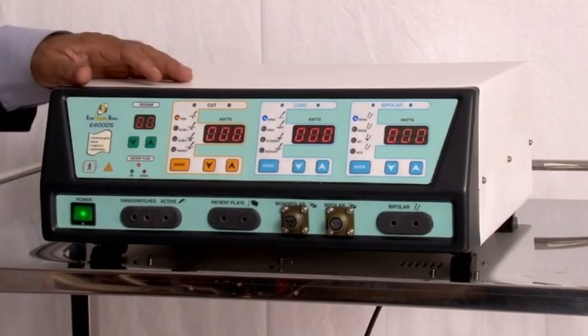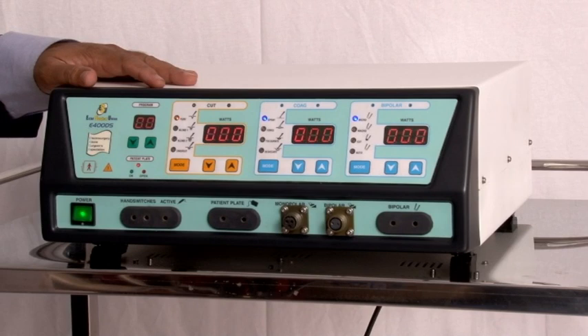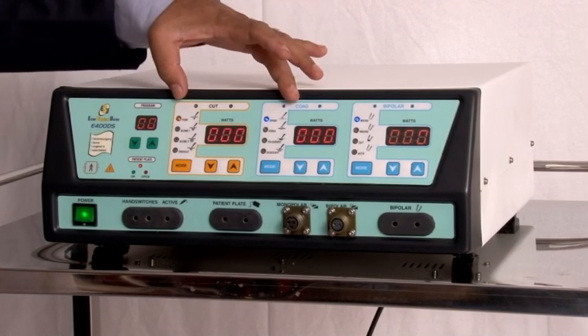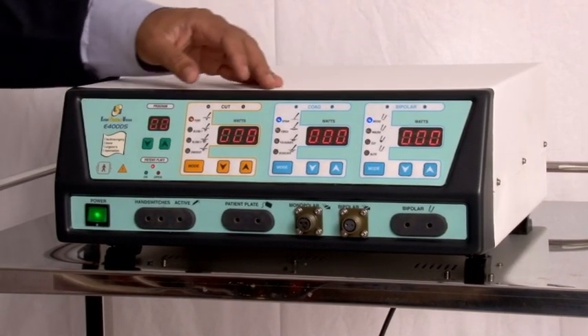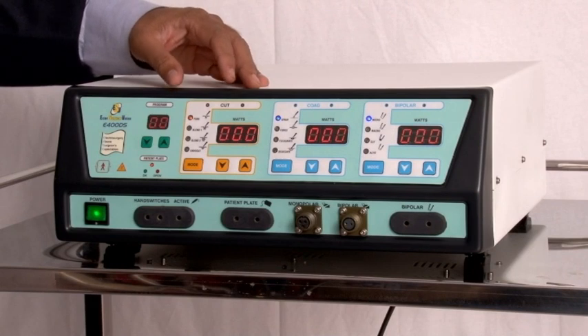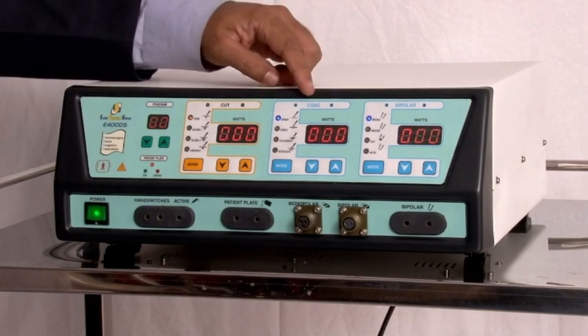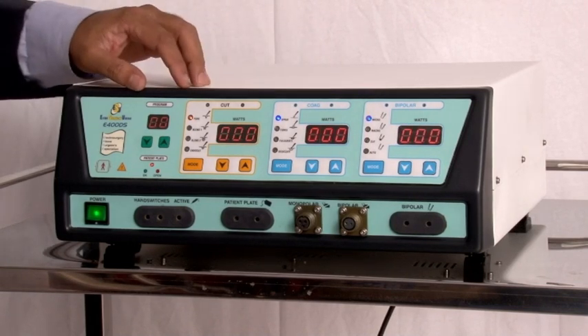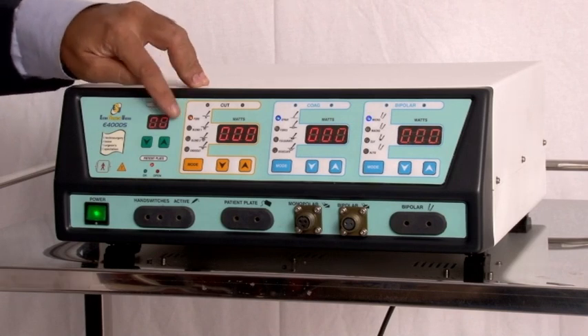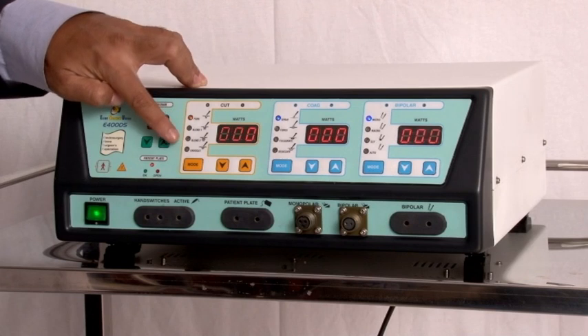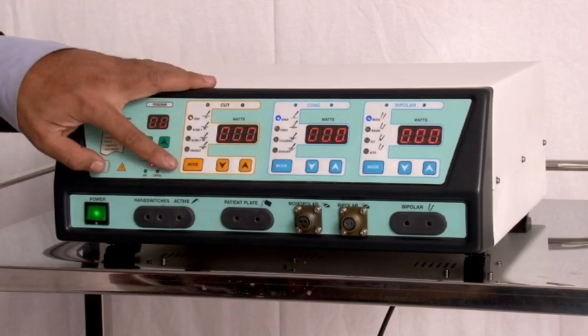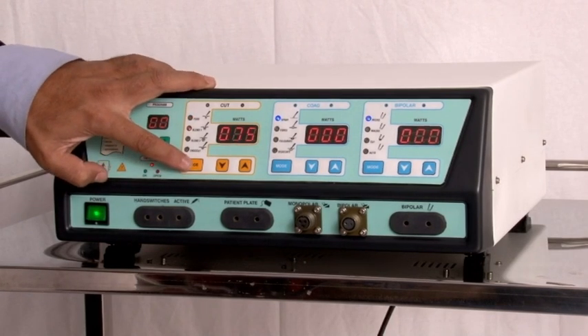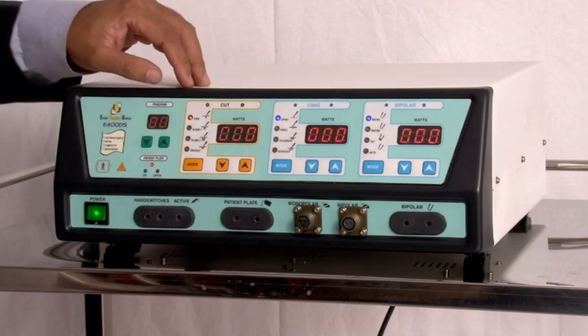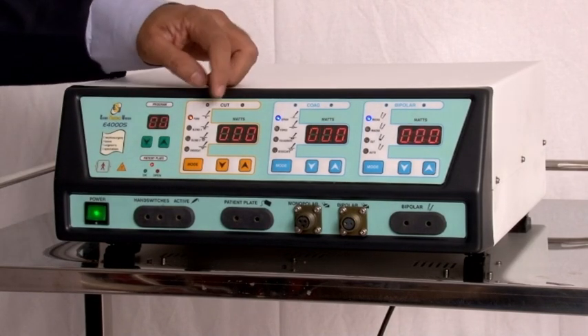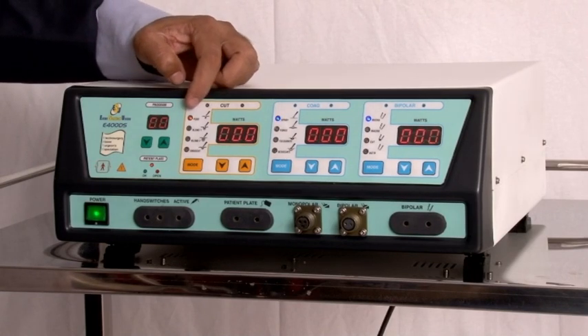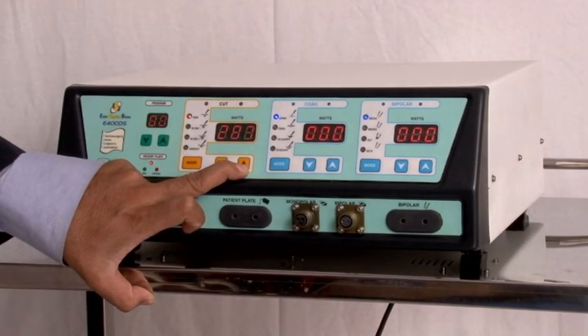The electrosurgical generator E400DS is divided into two major outputs: monopolar output and bipolar output. Monopolar output has two modes: cut mode and coagulation mode. In cut mode, we have four different types of output: pure cut, blend 1, blend 2 and endo cut. Pure cut mode is a high frequency alternating current with optimum peak voltages and pure sinusoidal waveform, which gives a rapid cutting effect without dragging of the active electrode in different types of tissues. Pure cut mode has a maximum power output of 400 watts.